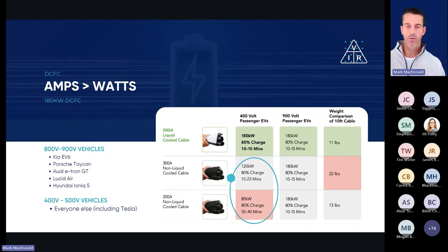Even if I take that 300 amp cable and plug into a 400 volt battery, 300 times 400, I'm still only getting 120 kilowatts out of it. In order to get the full 180 kilowatts out of a 180 kilowatt charger on any 400 volt vehicle in North America, I need to move up to a liquid-cooled cable, or offer what we call a boost mode or overdrive mode on that 300 amp cable.